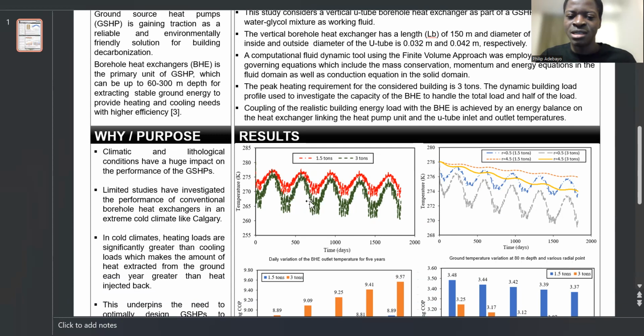So if you look at the outlet water temperature, when the ground heat exchanger is handling 1.5 tons, and when it is handling 3 tons, we could see that in all cases throughout the 5-year study period, for the 1.5 tons case, we do not have any instance where the temperature coming out from the bore heat exchanger is less than the minimum recommended temperature required for the heat pump. But for the 3 tons case, we could see that there are times when the temperature of the working fluid is lower than the minimum recommended temperature for the heat pump. This is for about 28% of the time over the 5-year study period.